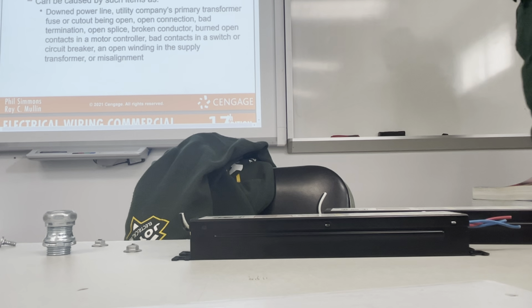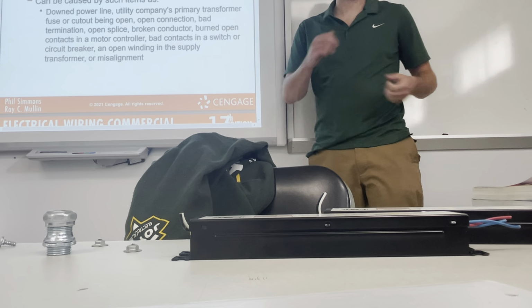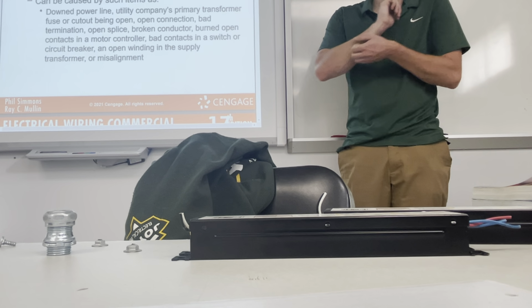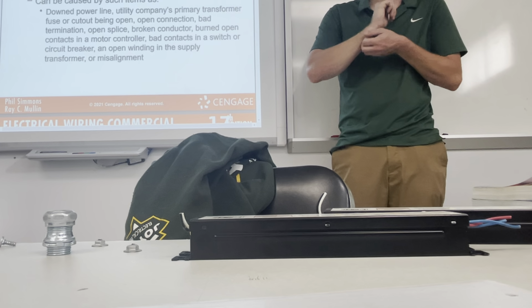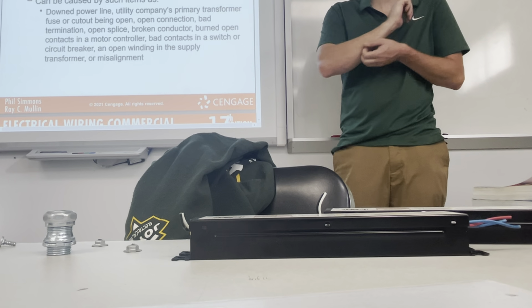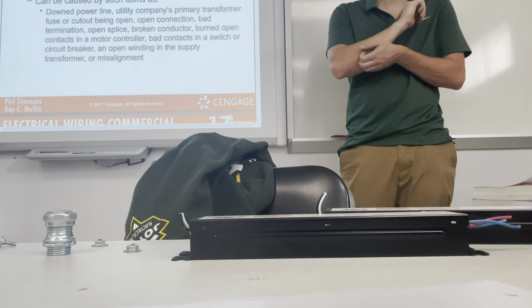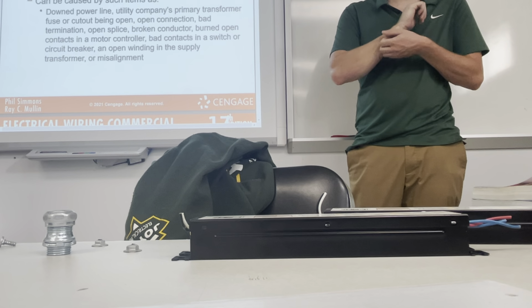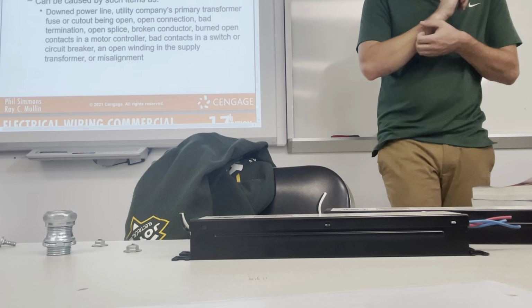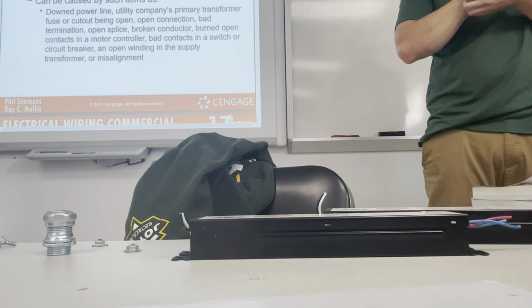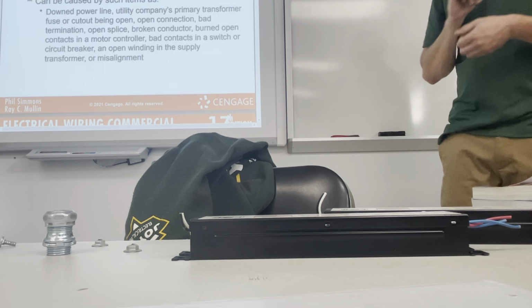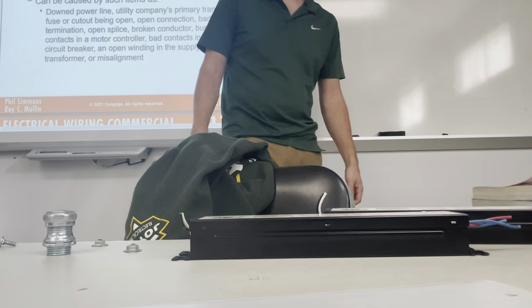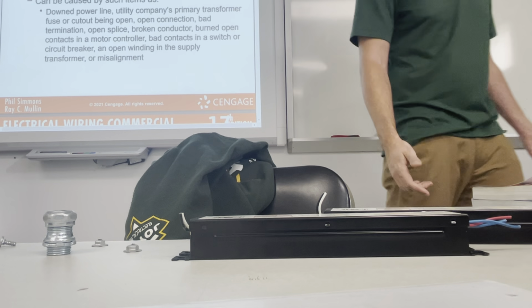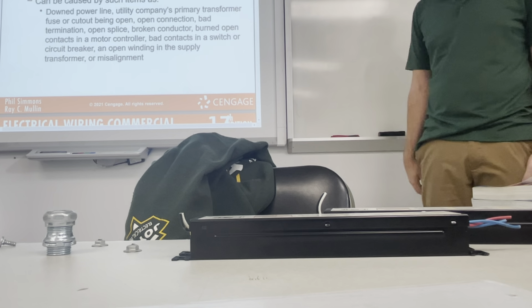So now you have 3 legs of power coming to feed a motor, right? You took one away. What do you think is going to happen to the other 2 lines that are still running? Do you think their amperage is going to be the same, go down, or skyrocket? Skyrocket, right? There's a chance if your overload doesn't catch it fast enough, it can blow that motor sky high. But when they call it single phase in here, I call it losing a leg. Does that make a little bit more sense? We lost a leg at the motor.